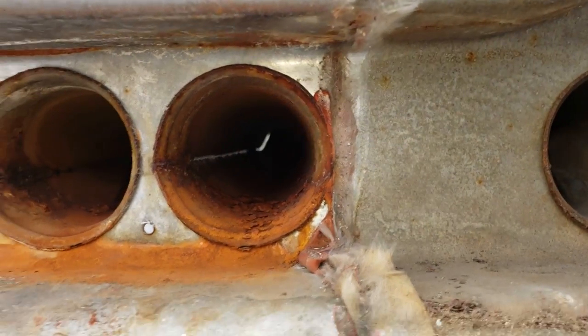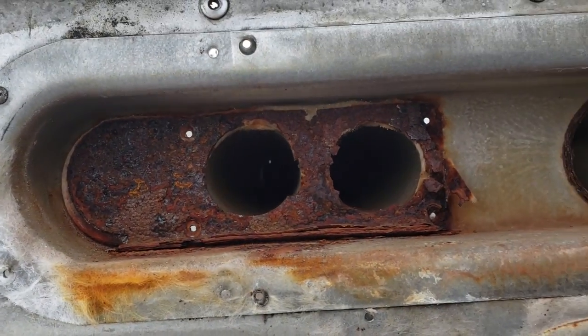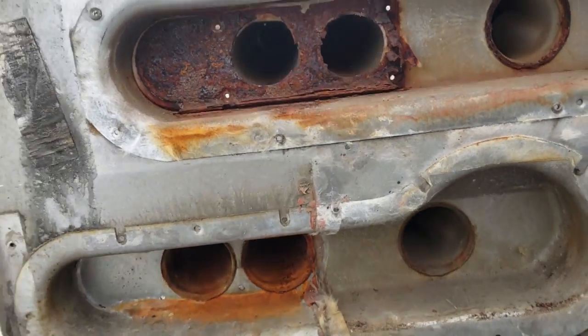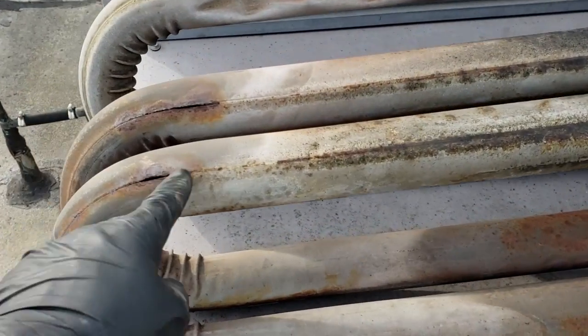Don't think you're supposed to be able to see daylight through a heat exchanger tube. It just doesn't seem right. Must be a crack, right? Typical spot, right at the seams.